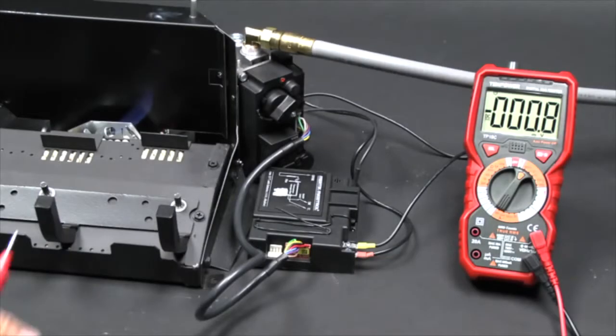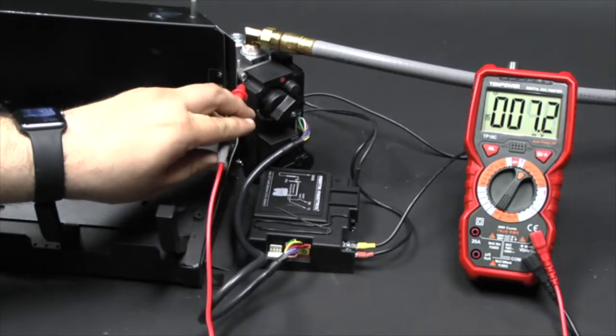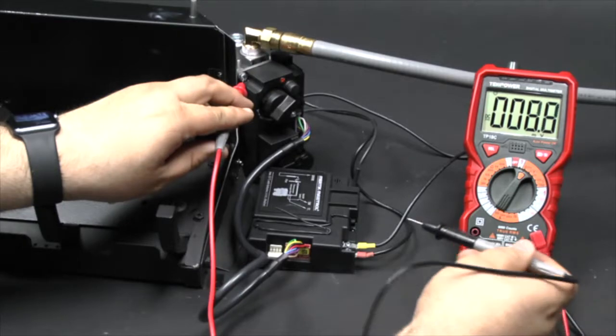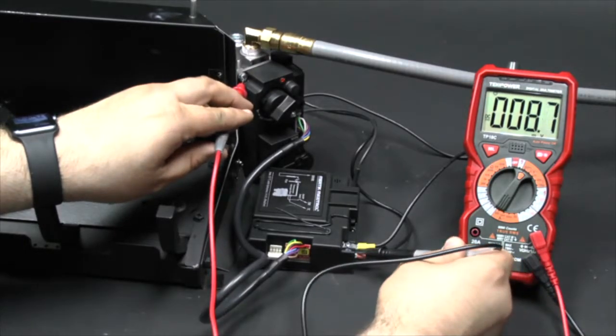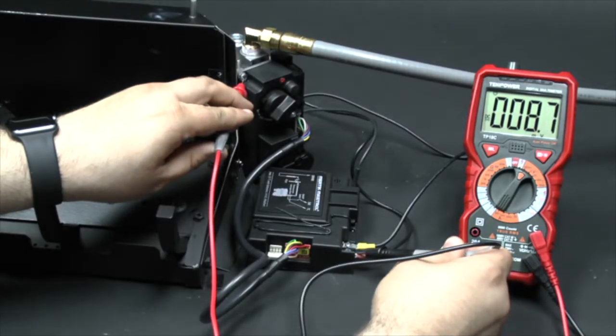Place the red lead on the ground screw located at the top left corner of the valve. Place the black lead on the large red wire attached to the control module.